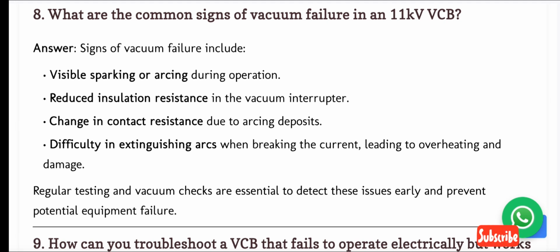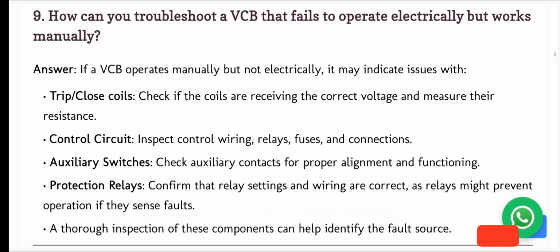Answer. Signs of vacuum failure include visible sparking or arcing during operation, reduced insulation resistance in the vacuum interrupter, change in contact resistance due to arcing deposits, difficulty in extinguishing arcs when breaking the current, leading to overheating and damage. Regular testing and vacuum checks are essential to detect these issues early and prevent potential equipment failure. 9. How can you troubleshoot a VCB that fails to operate electrically but works manually?